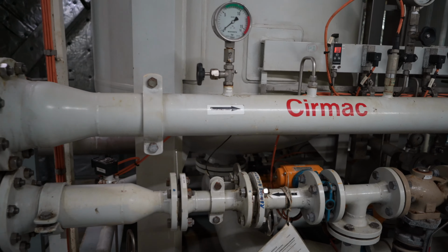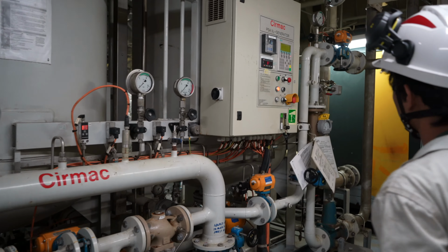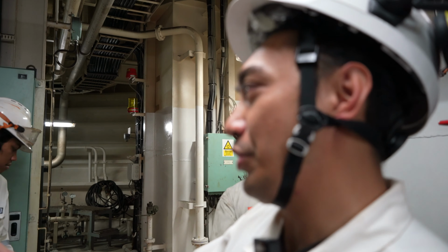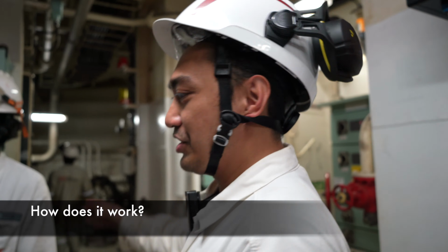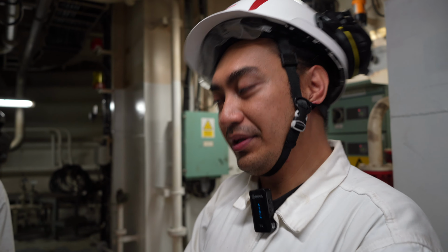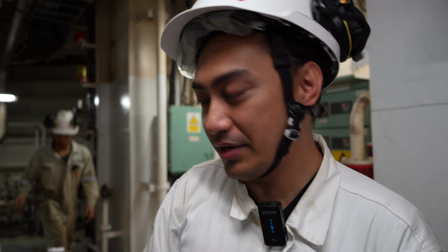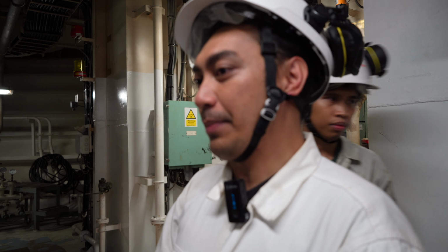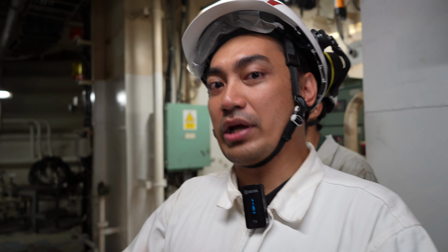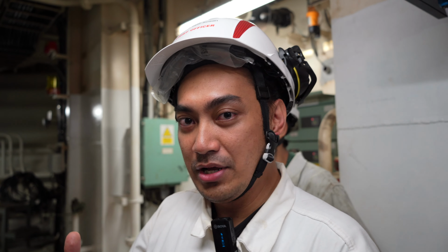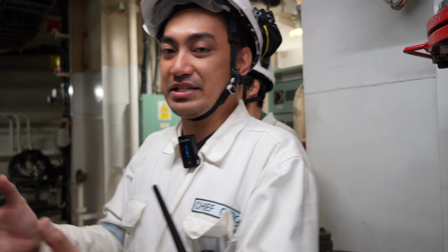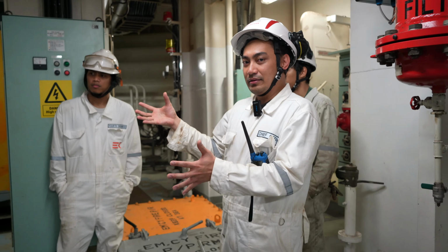Then, guys, we gotta go along the processing. So we're already well informed when it comes to the startups. Now I will show you how the process flows. As the second engineer already instructed, power first, then the seawater cooling for the air compressor and the air dryers, and then we'll ensure the startup of the compressor and then the dryer. Sometimes it is also advisable to have the air dryer already started beforehand, so it can already build the momentum in order to reduce the dew point within the system before permitting the air itself.